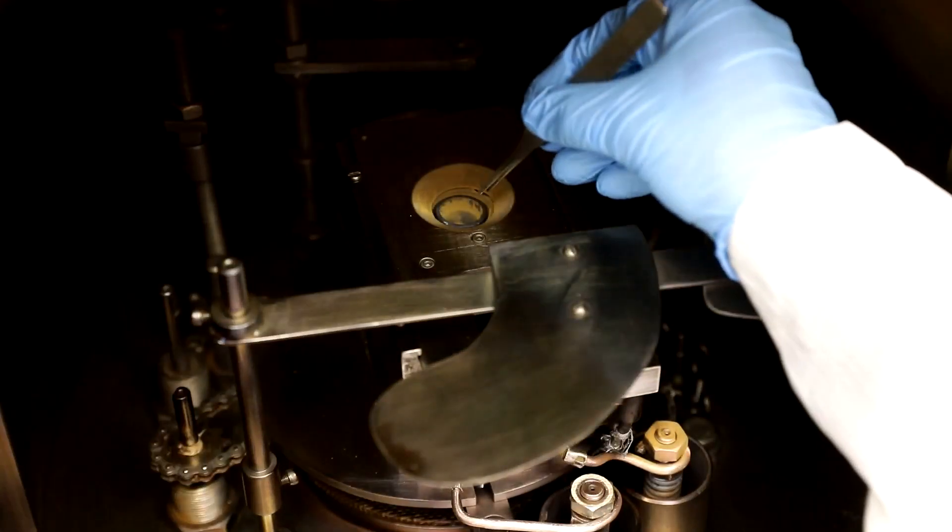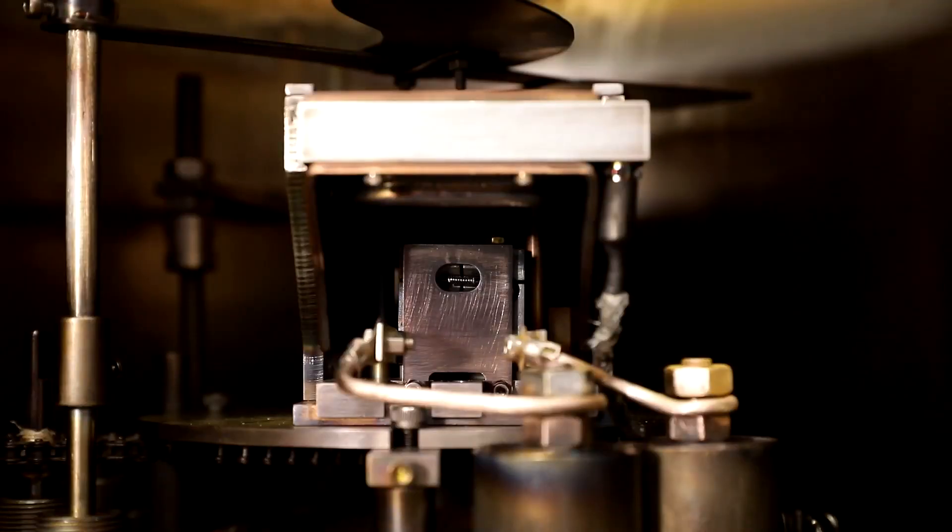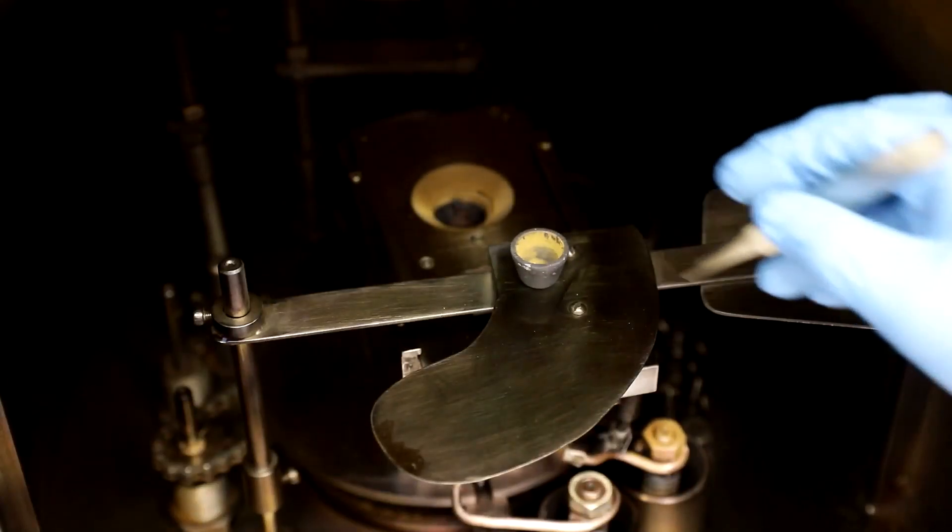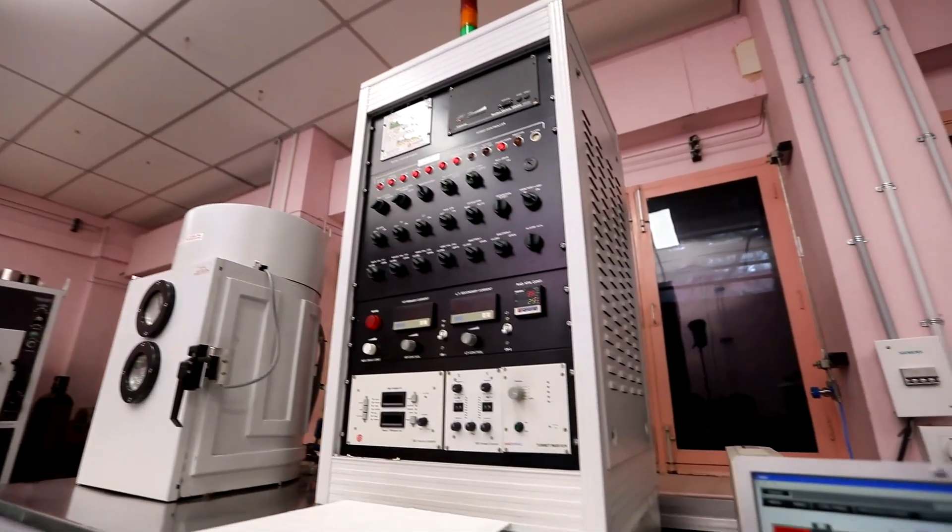This is the crucible where we keep the source material which is evaporated using the focused electron beam on our target substrate which is kept here. This crucible is made of tungsten. Crucibles are generally made of high melting point metals, or in some cases ceramics are also used.